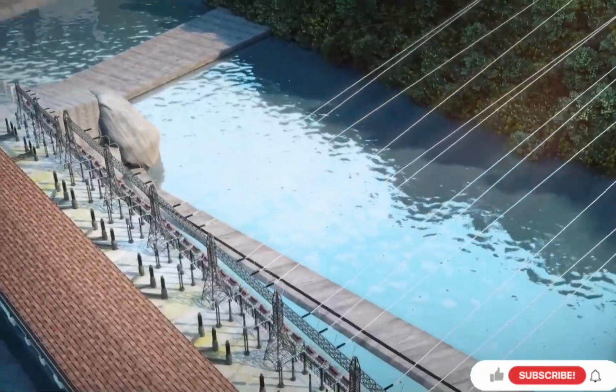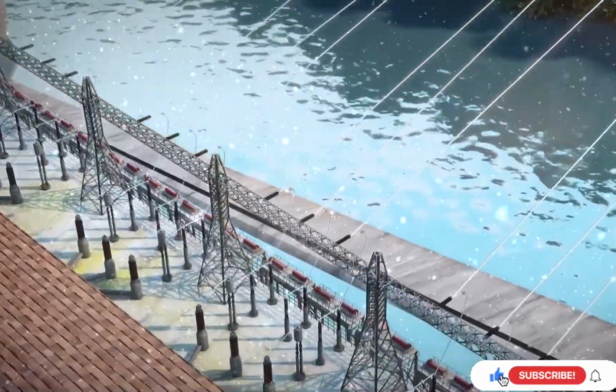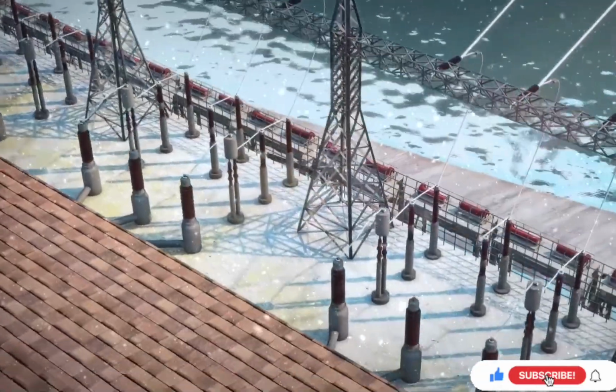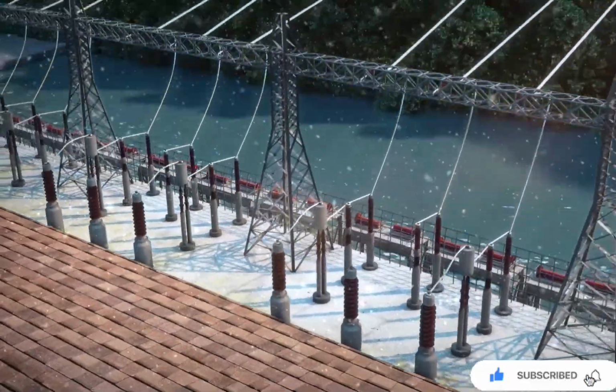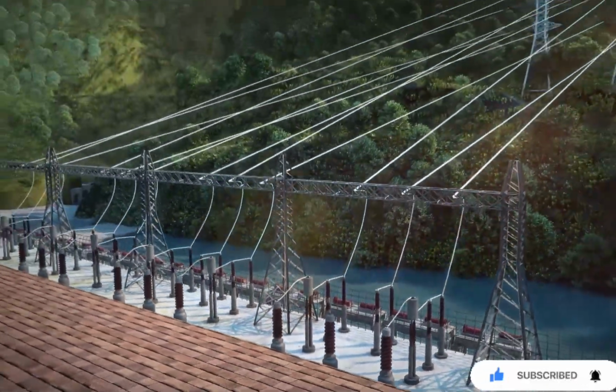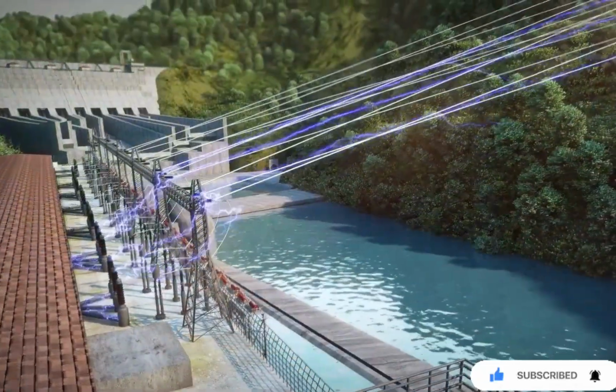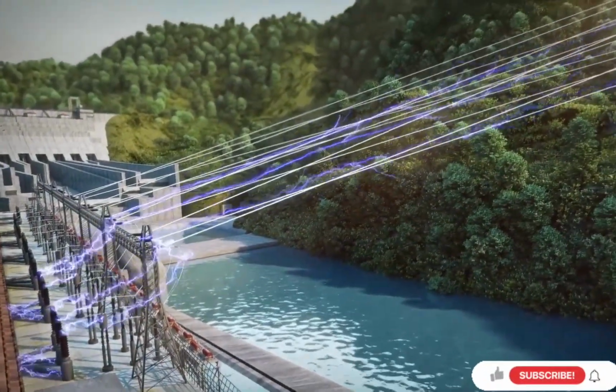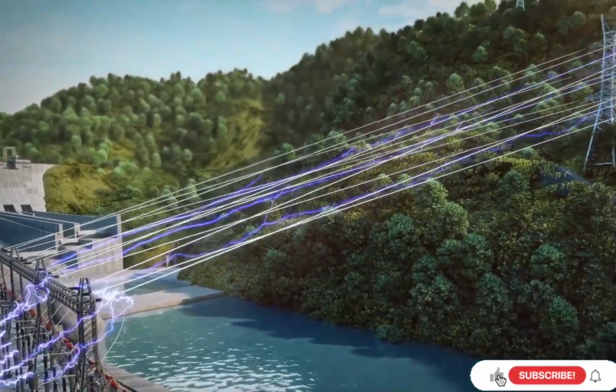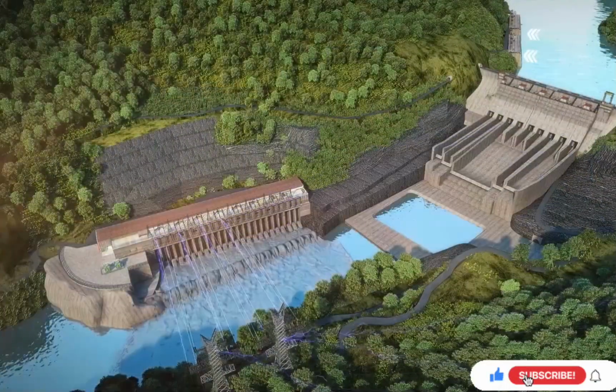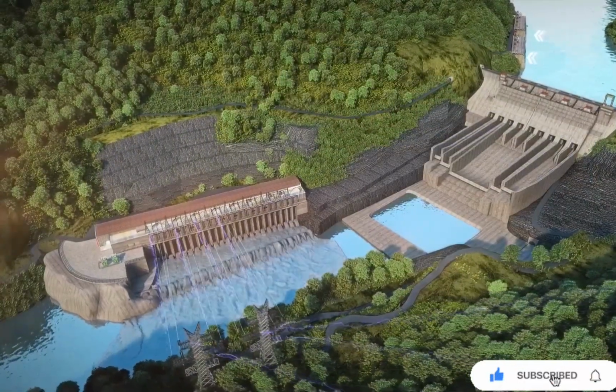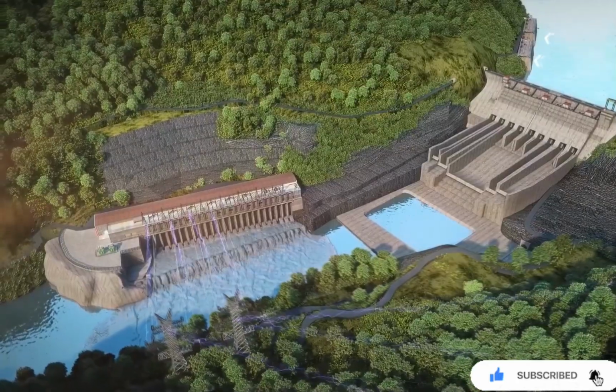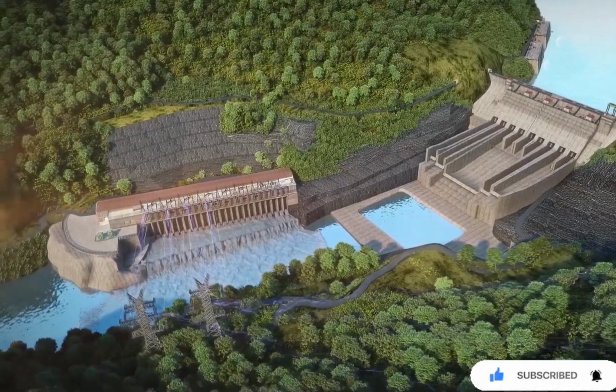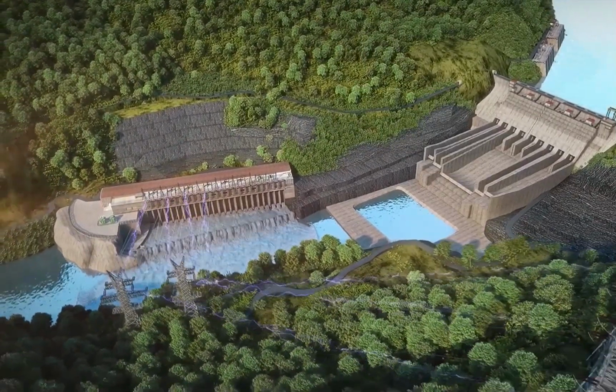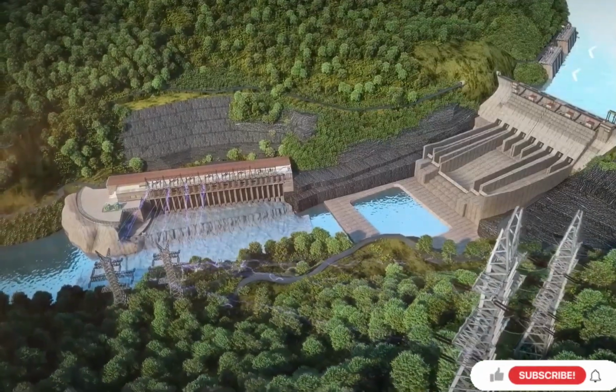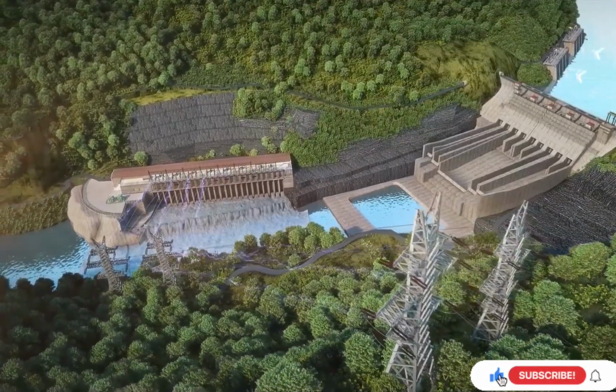Power generated from the project is evacuated through 6 400 kV and 2 132 kV transmission lines. 400 kV transmission lines are connected to the nearest PGCIL pooling station at Viswanath Chariali through 400 kV double circuit transmission lines. After electricity is generated, water flows to the river through the tail race channel. Out of the 8 turbines, one of the turbines shall always be in operation, which will ensure that a continuous river flow is always maintained throughout the year for ecological balance.